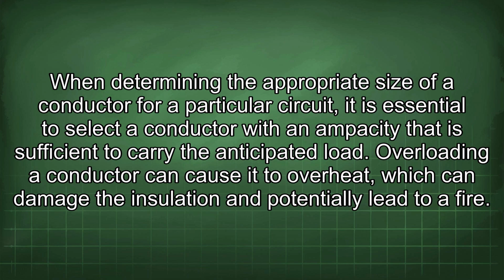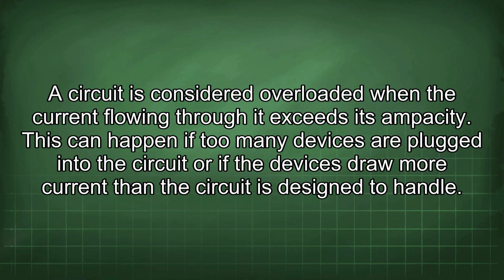Overloading a conductor can cause it to overheat, which can damage the insulation and potentially lead to a fire. A circuit is considered overloaded when the current flowing through it exceeds its ampacity. This can happen if too many devices are plugged into the circuit or if the devices draw more current than the circuit is designed to handle.